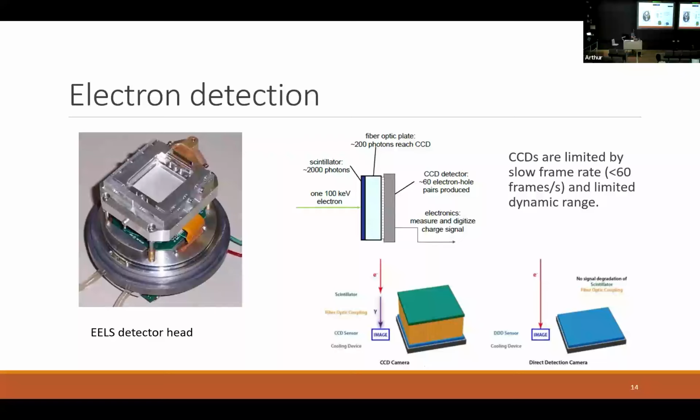The CCD looks something like this. This can be just the same as a standard TEM imaging CCD. So the electrons come in, they go through a scintillator, and then they convert to light, and then we can measure the signal intensity on a pixelated detector. These days we're getting even fancier, or more expensive, and instead of this CCD type arrangement, we can use direct electron cameras. These don't have all of this conversion, so they're a lot more sensitive, which is great. They're also a lot faster, so we can collect our data a lot faster. But the downside is, A, they're way more expensive, and B, they're also a lot more sensitive to damage. So we have to be a little bit more careful when we're using that kind of system.